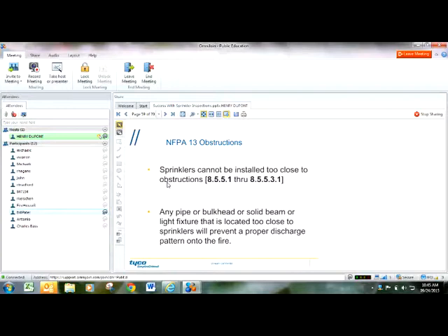There's no rule. You've got to go back to NFPA 13 and go to the actual page where there's a formula that you've got to work out, and it's going to be different for every distance away from the obstruction and the depth of the obstruction. So I encourage you, if you don't have a copy of NFPA 13, to get one. And if you suspect that sprinkler heads are being obstructed as part of your inspection, you need to get that table out and do that math.